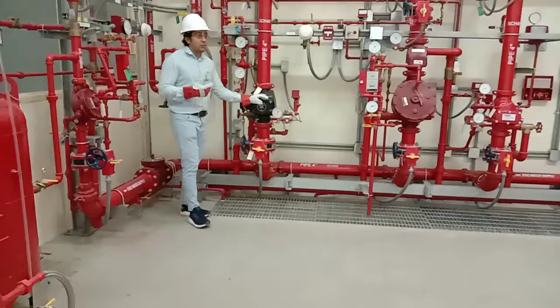Now, the deluge valve is a specialized one, right? What is the meaning of that? They don't have closed sprinkler heads. The sprinkler heads are open, all the heads are open. The meaning of deluge itself is flood, right? So all the valves are open, and when there is a fire, all the sprinklers discharge water and the fire will extinguish easily, but a high quantity of water will discharge from the deluge valve. So the capacity of this deluge valve and the pump size will be higher because here we have the complete flooding system of the room in case of fire.